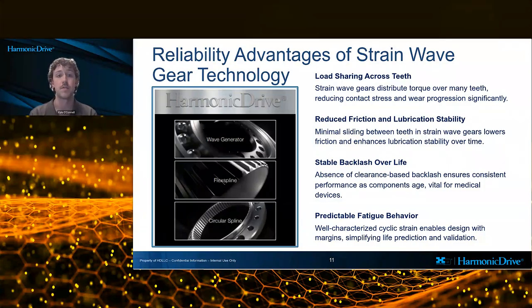From a fatigue standpoint, cyclic strain experienced by the flex spline in a harmonic drive is well characterized, and it can be designed with ample margin and operating within our rated limits. We work with our medical customers to assure this is always the case. These characteristics lead to more gradual and predictable degradation long-term, which simplifies life prediction and validation. For system designers, this is going to mean fewer surprises on your end during long-term testing and field operation, and a much higher degree of confidence that the performance at the end of your system's life is going to meet those clinical requirements and help you operate the way you want to.